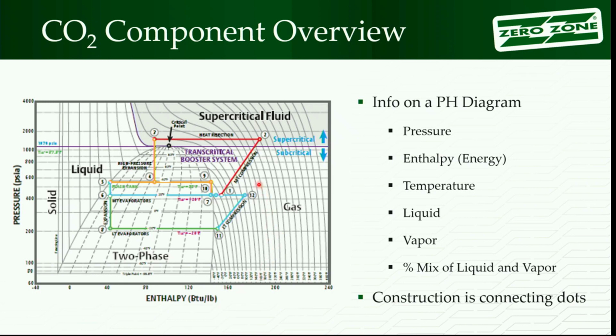The other item we're going to look at is temperature, which is pretty important. These curved lines, as they sweep through, represent a constant temperature. So if it's 100 degrees, and we'll see it on another one, there's a line that represents 100 degrees. So if your system is operating at 100 degrees and you wanted to draw it on here and say where that point exists, you'd follow the 100-degree line. Then you'd look at what the pressure gauge reads, and you put that point in there.